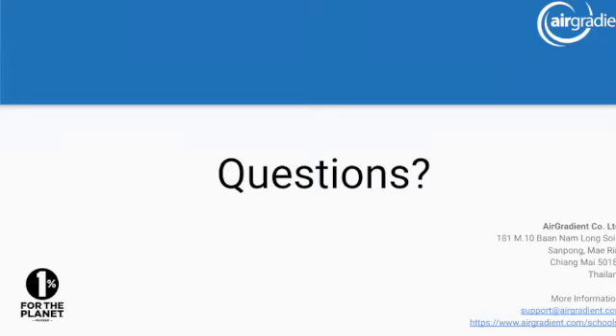Now there are a couple of problems. First, when you receive the unit, due to transportation and vibrations, in some cases the CO2 sensor is just totally off, and sometimes people don't want to wait a week to calibrate it. So what you can do is, we have in the Arduino library a special sketch, an example code you can flash on the device, then bring it outside with a power bank, wait maybe 5 minutes so the air gets inside the enclosure, and then run that sketch, which will reset it immediately to 400 ppm.